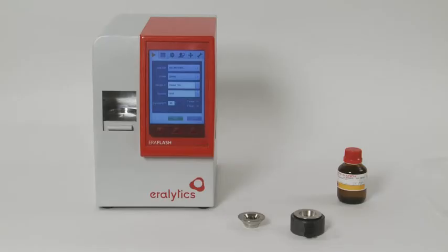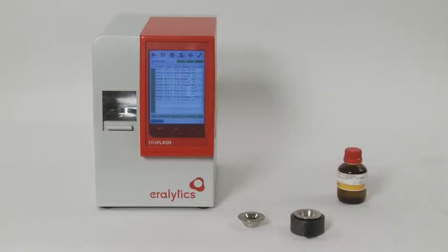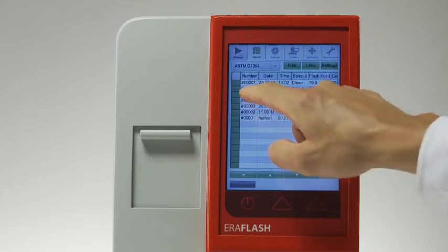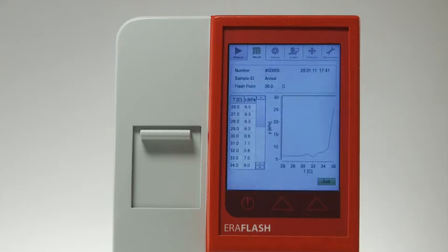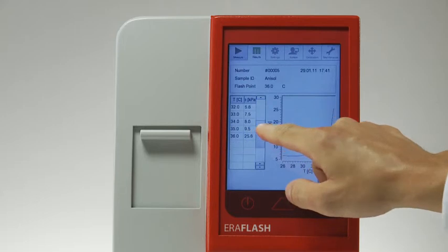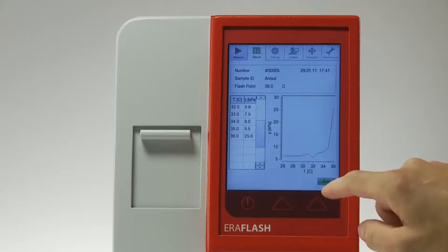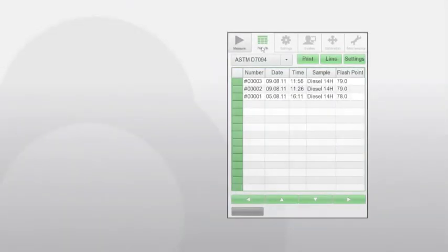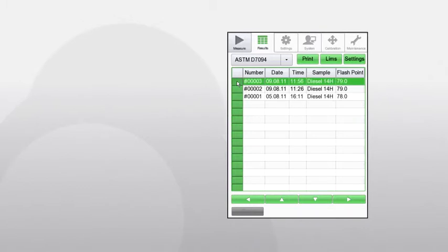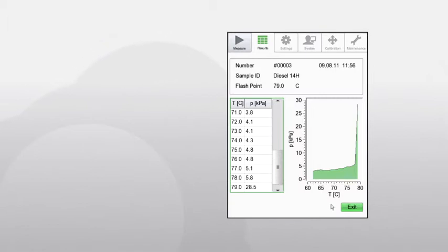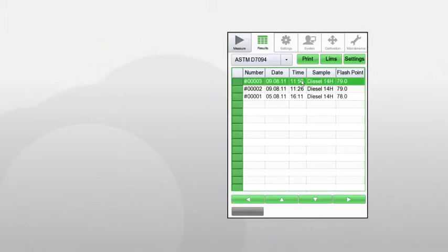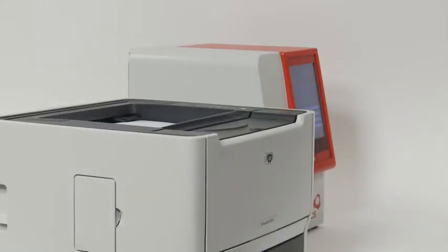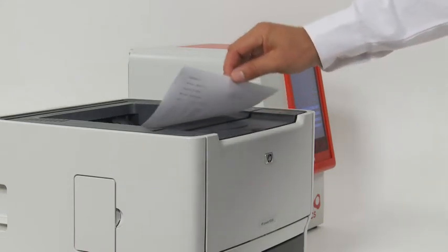Result Handling: In the result menu, several thousand results can be stored and reviewed. Simply go to the result menu—each line displays a result. Using the settings button, you can select specific parameters you need to be shown in the result menu. Browse through the result memory using the cursor keys at the bottom of the list. To view the pressure development graphic of an older measurement, press the box to the left of the desired result. The data can also be printed on a directly connected printer or via Ethernet connection to a LAN or network printer.